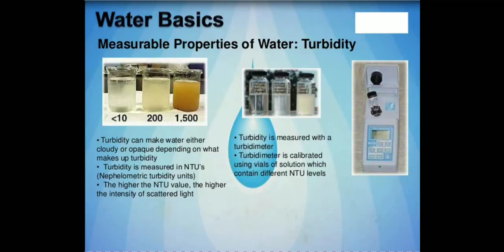Turbidity, nephelometry, compares intensity of scattered light. What is the principle of that instrument? It compares intensity of scattered light. Instrument sensitivity must be able to detect turbidity differences of plus or minus 0.02 NTU.